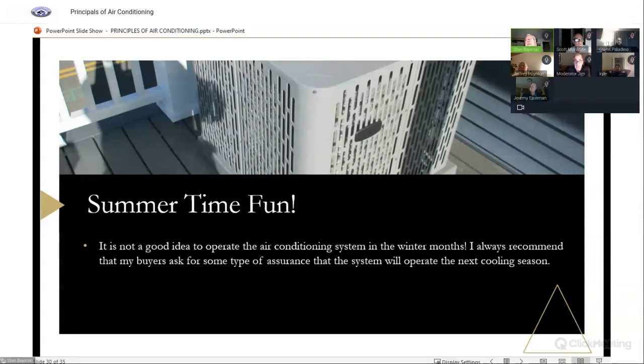No, definitely not. The other question I have is, I do this, but if I can't, I sort of just use my experience, determining the age of the system, normally from the serial number, date of manufacture on the tag. I know the state standard in Connecticut doesn't require it, but I do like to do life cycles. So do I. Does everybody know about the Building Intelligence Center by any chance? Yep. Because 90% of the units that I have to determine age for are on that website, determined by serial number. Sometimes it's pretty evident. Sometimes it's written on, manufactured on such a date. If I see it, I will write it in my report. If I can't determine the age, I put undetermined.